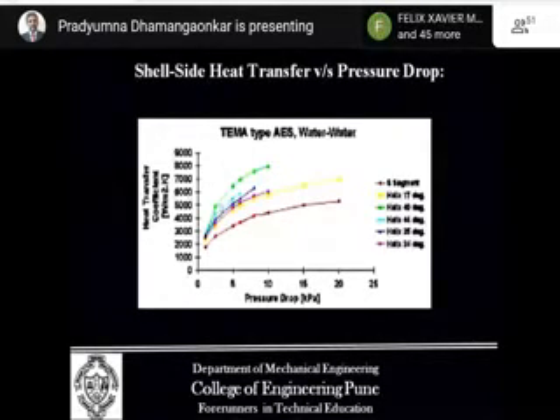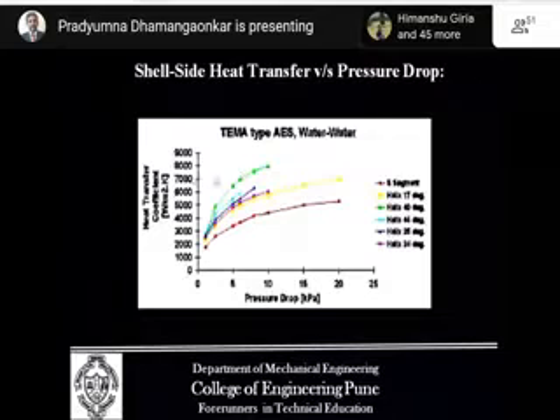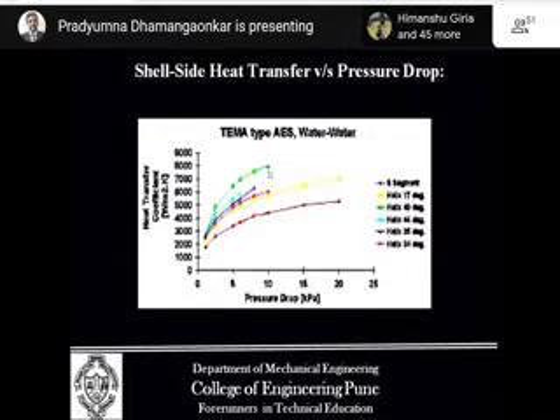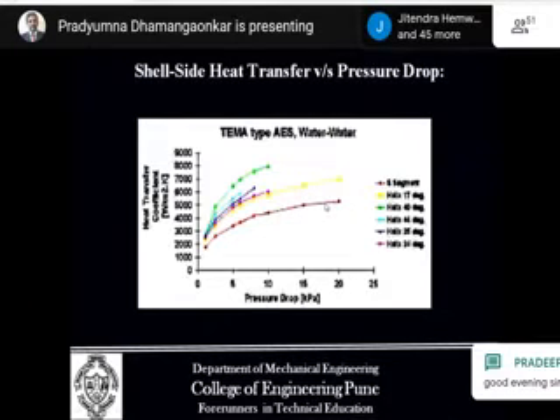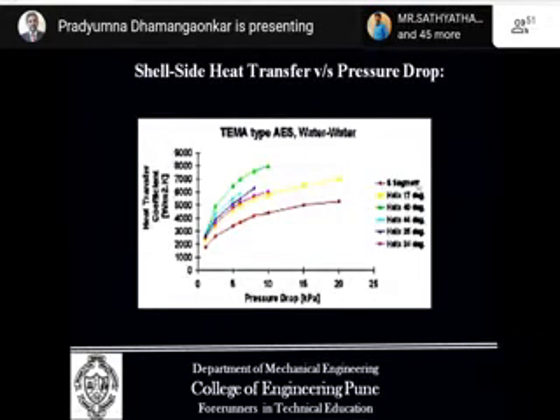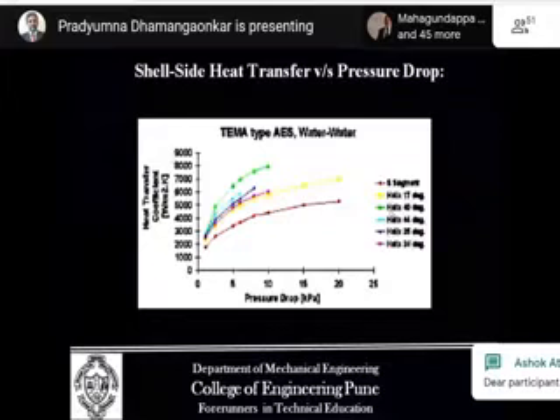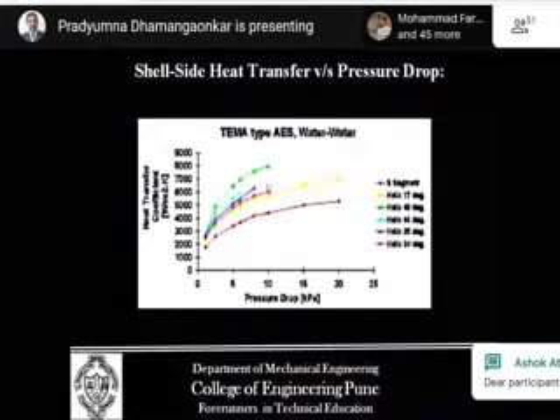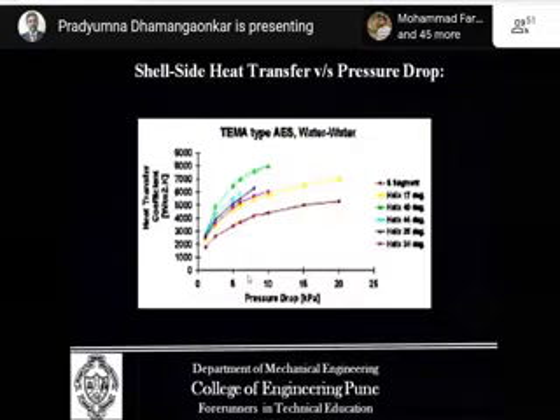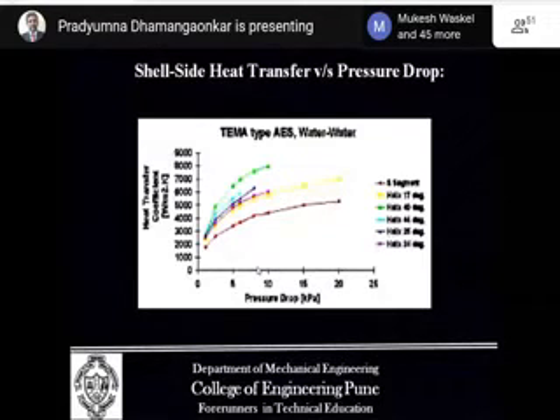If we look into this graph, this green line is giving the highest heat transfer coefficient, and at the same time, its pressure drop is also less as compared to this yellow one, which is at 17 degrees, and this brown one, which is nearly straight. So it is preferred to go for the helix with 40 degrees. This will give us a higher heat transfer coefficient as well as a lower pressure drop. In the helix changer, the baffles are placed at 40 degrees with the vertical, and this is what the helix angle is called.